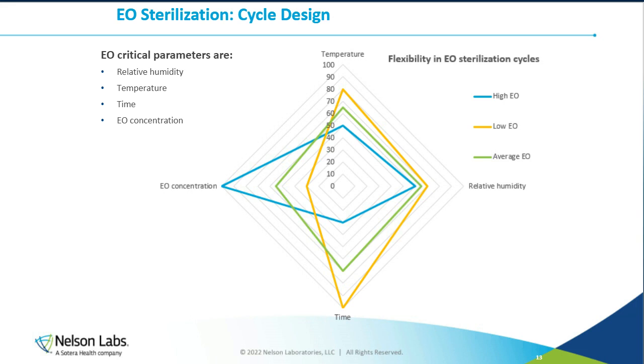So instead of having only the dose, as for radiation, we have a variety of different aspects that we need to consider. It's a bit more complex to fine-tune and find the right parameters to design the best cycle, but we can see with this chart that we can play with the parameters. If we are reducing the concentration, we can either increase the temperature or play with the time, and we have to find the best compromise. Willing to reduce EO too much can extend the duration of the cycle, which is not the initial intention.